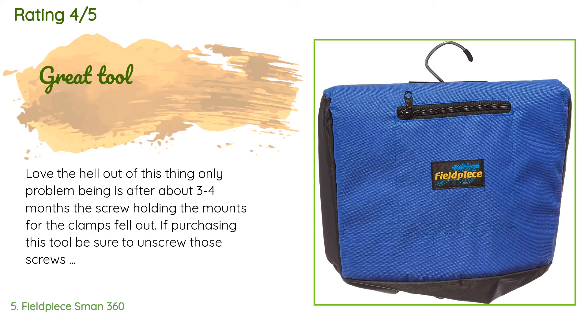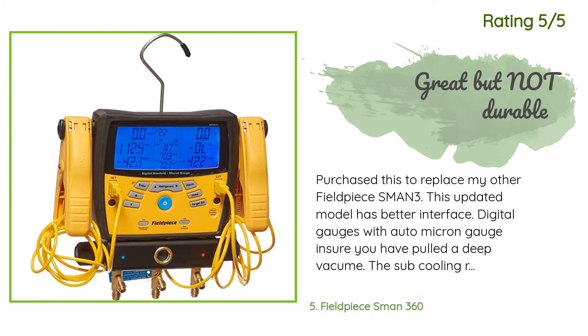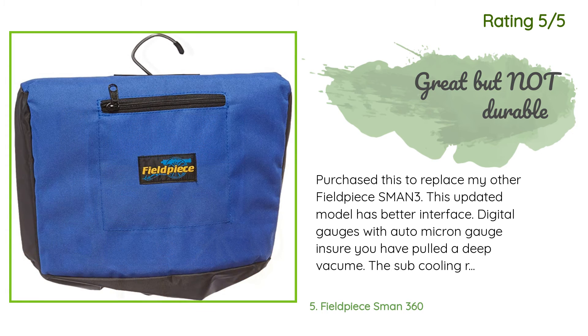Another happy customer said: 'Purchased this to replace my other Fieldpiece SMAN3. This updated model has a better interface — digital gauges with auto micron gauge ensure you have pulled a deep vacuum. The sub-cooling readings provided with the clamp-on temp gauges is the only method to accurately charge R410A. One or two negatives: the gauge LCD screen is susceptible to permanent damage if dropped or something hits it — this happened to my first one.